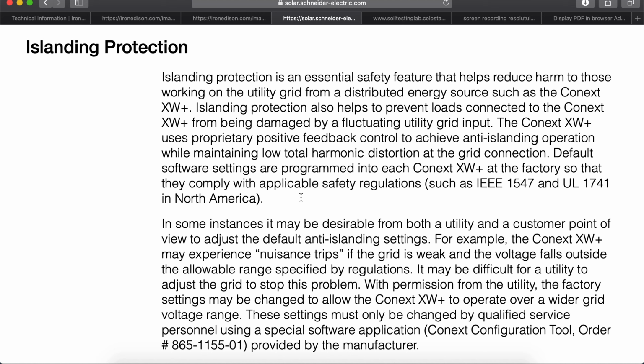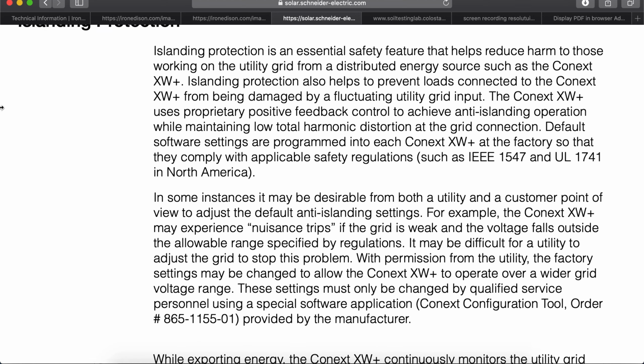In some instances, it may be desirable from both a utility and a customer point of view to adjust the default anti-islanding settings. I've done this. For example, the Conext XW Plus may experience nuisance trips if the grid is weak and the voltage falls outside the allowable range specified by regulations. It may be difficult for a utility to adjust the grid to stop this problem. With permission from the utility, the factory settings may be changed to allow the Conext XW Plus to operate over a wider grid voltage range. These settings must only be changed by qualified service personnel using a special software application, the Conext Config tool, provided by the manufacturer. I own one of these tools.